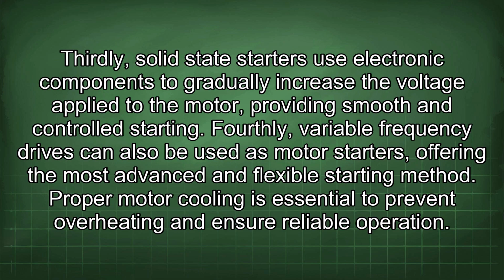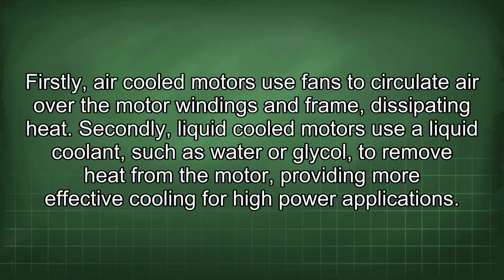Proper motor cooling is essential to prevent overheating and ensure reliable operation. Firstly, air-cooled motors use fans to circulate air over the motor windings and frame, dissipating heat. Secondly, liquid-cooled motors use a liquid coolant, such as water or glycol, to remove heat from the motor, providing more effective cooling for high-power applications.